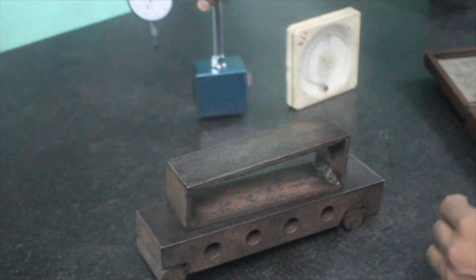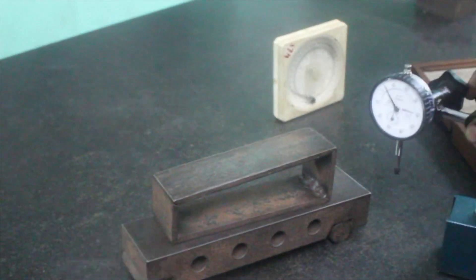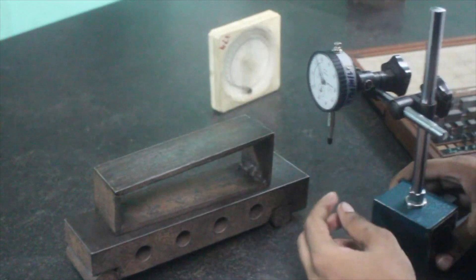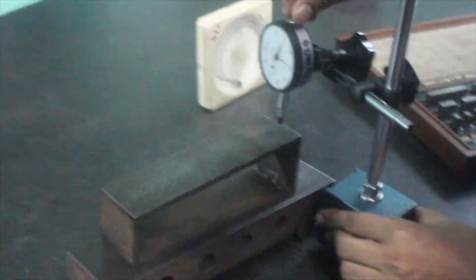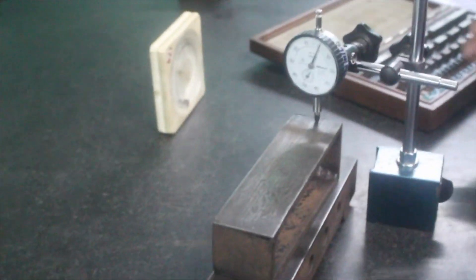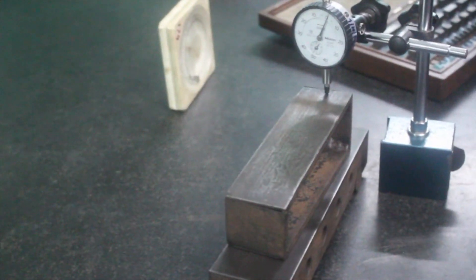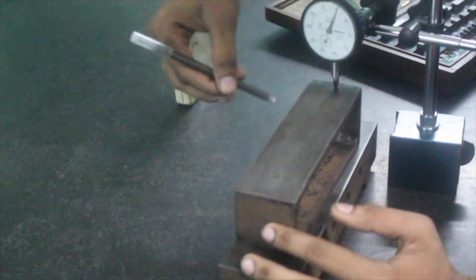We are going to check whether the surface is flat or not. For that, we use a dial gauge with a plunger available here. First, we keep this in the initial position and set it to 0 value. Now we have the initial base reference value 0. We will draw two reference lines, one here and another here. Then a line joining these two points will be drawn.